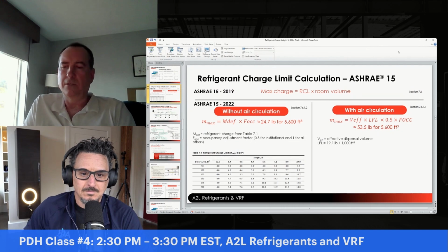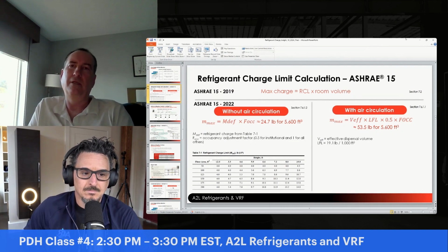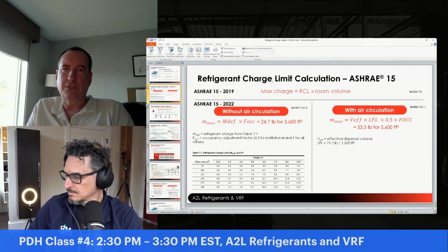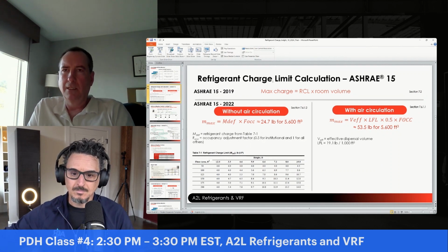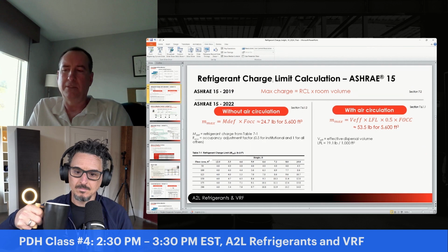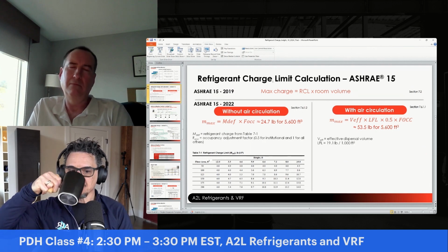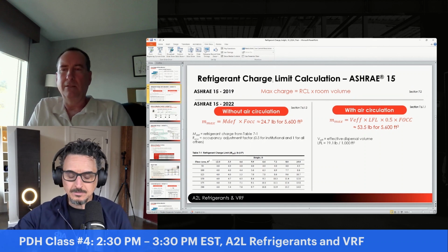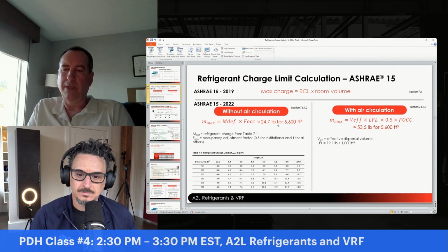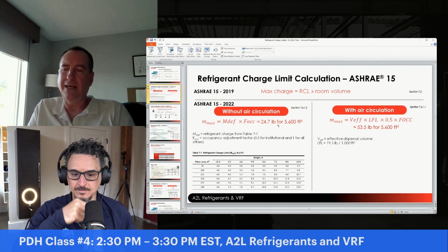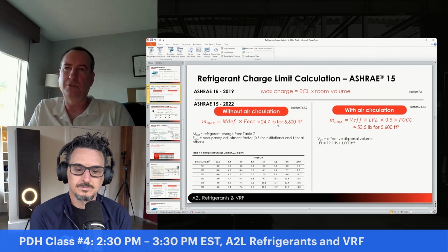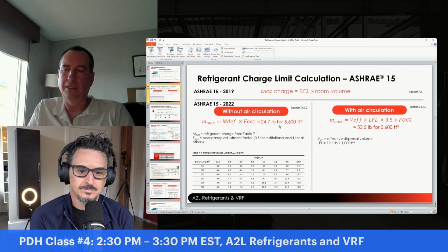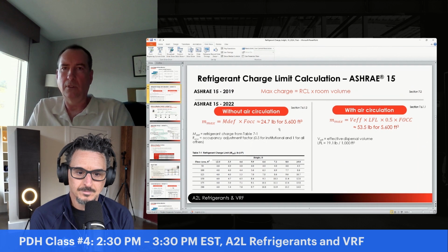So I mentioned RCL, refrigerant charge limit. In previous versions of ASHRAE, meaning 2019, the max charge was simply your RCL times your room volume. With 2022, we've added new calculations here, which helps manage these new refrigerant applications. In this example, without air circulation, the maximum charge for a room is calculated as the refrigerant charge in this table times your occupancy limit, which is just a factor - that's how you get that number. Occupancy factors are 0.5 for institutional and one for everything else.